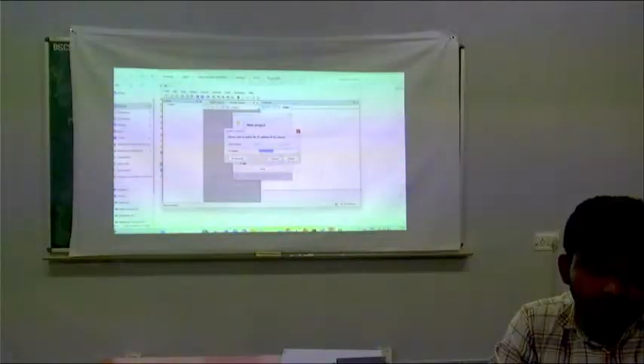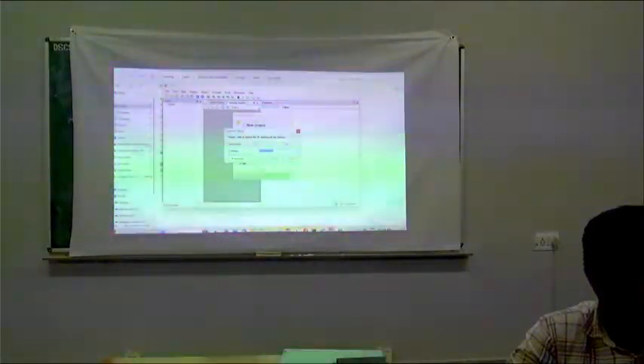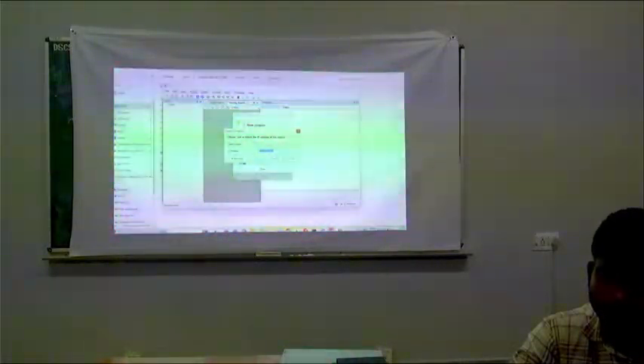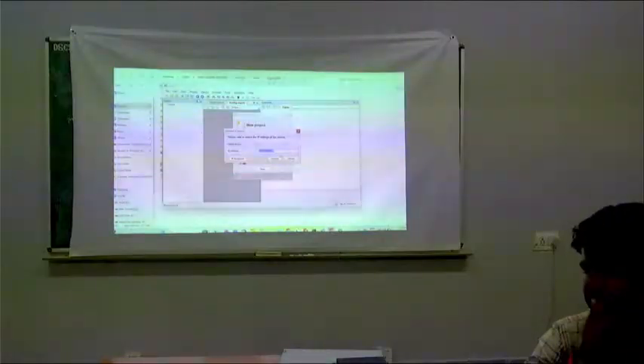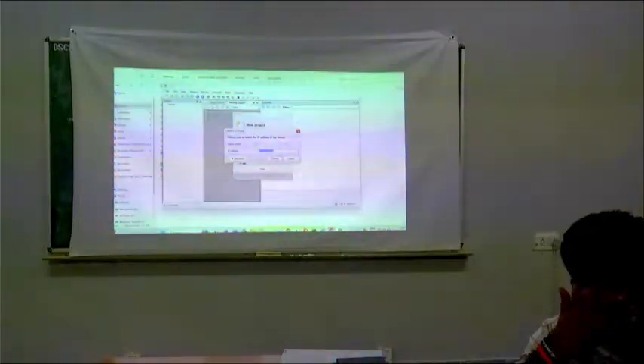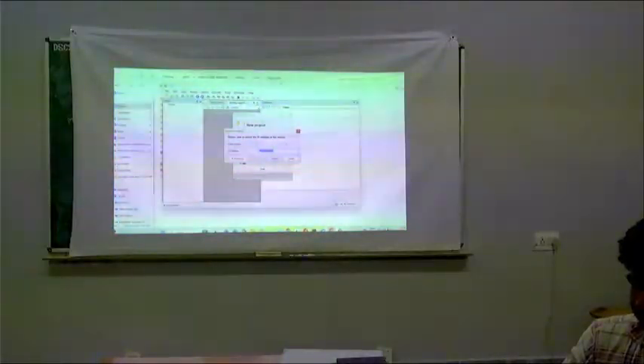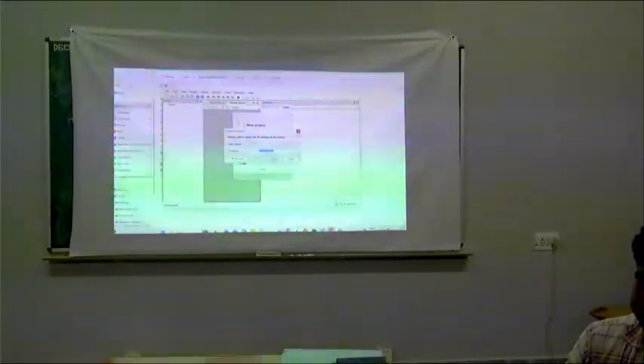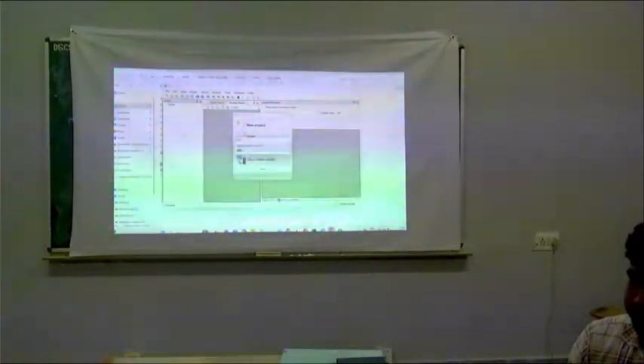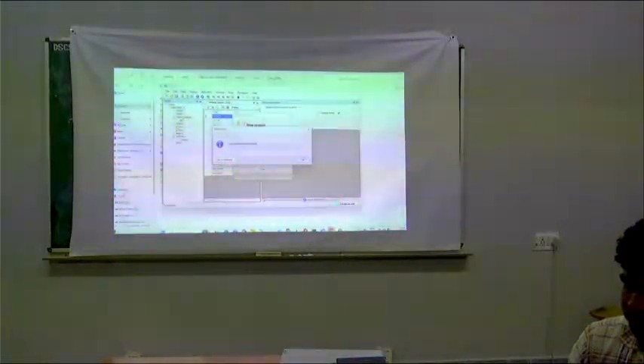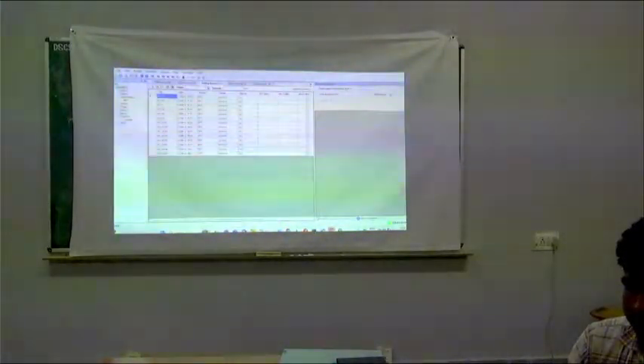Accordingly, in my gateway I create a configuration telling it to communicate to this device. When you are communicating to this device, I will go to that device, and here in this case, for example, I connected it to communication port 3. So I go there and add the meter to communication port 3. And then I specify what the meter ID is and what the baud rate is, that is, at what rate the communication is going to take place. All these parameters I specify in my gateway. Then when I apply the configuration from my laptop to my gateway, the gateway reboots and tries to search for that device on that communication port.